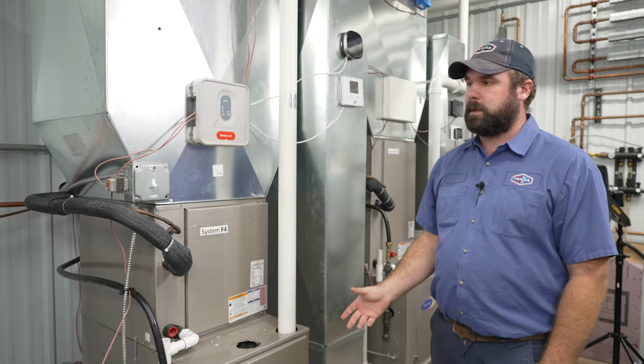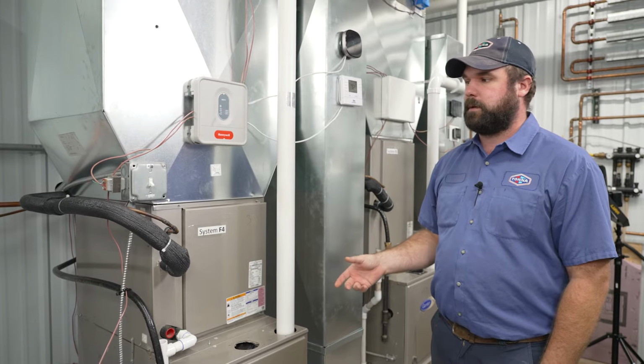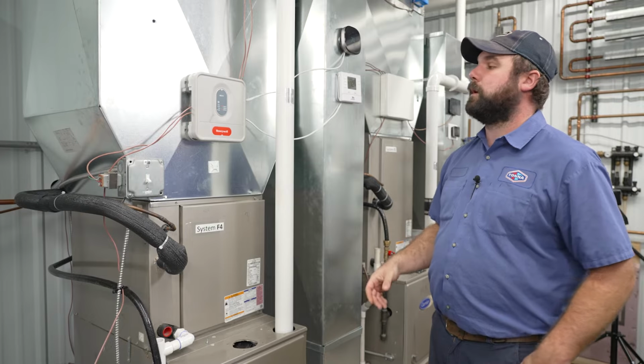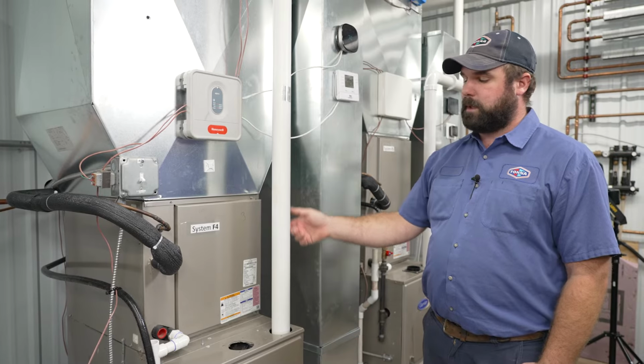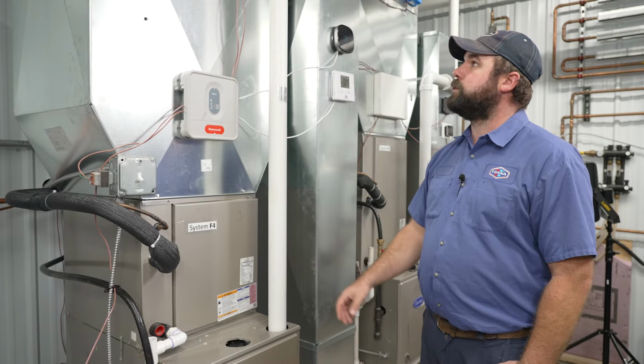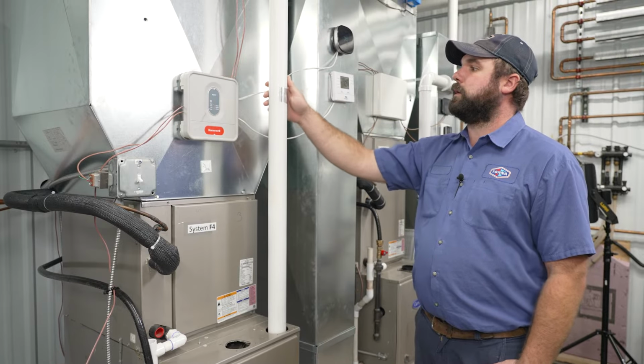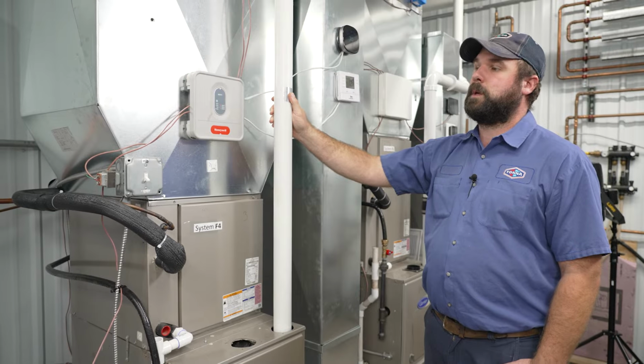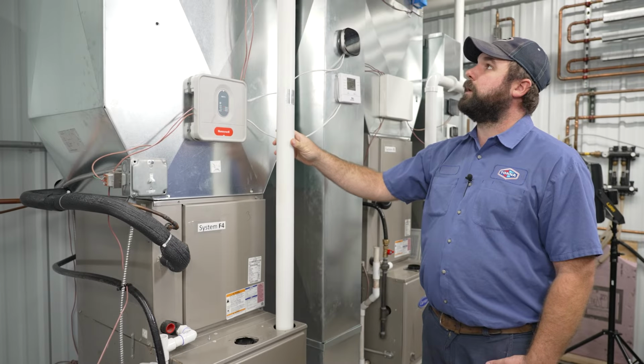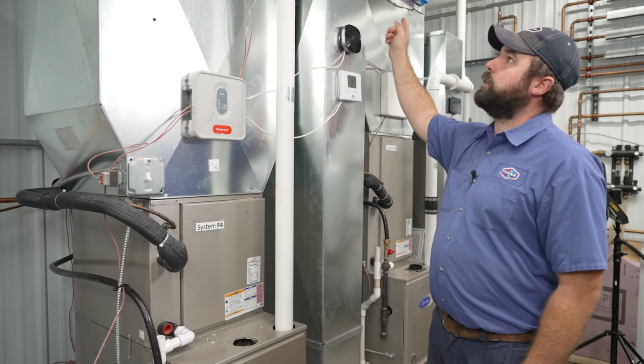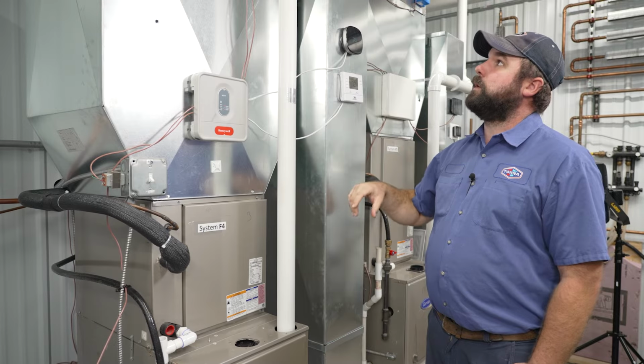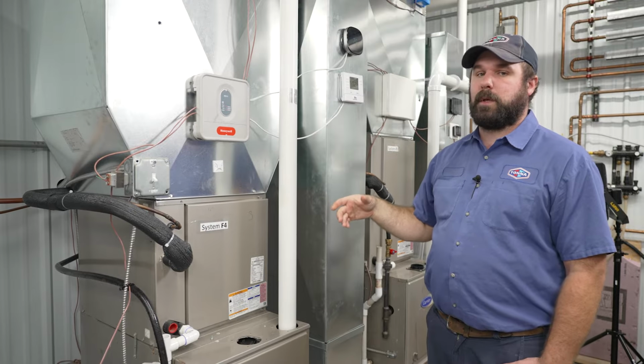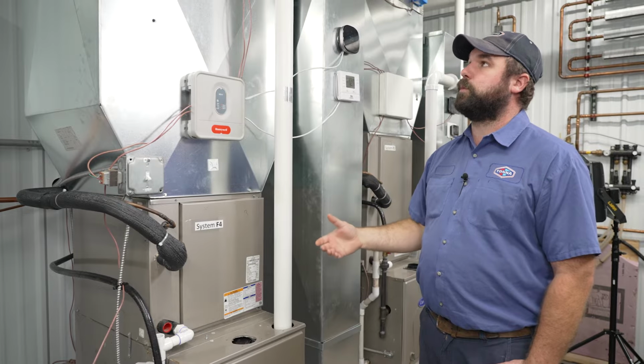Before we start to open things up, we're going to do a visual inspection of the outside of everything. Your exhaust pipe, your fresh air pipe, making sure we don't see any leakage or anything like that, making sure all the holes are sealed and everything's sloped right. Those are all key factors in making sure that the system's going to function properly.